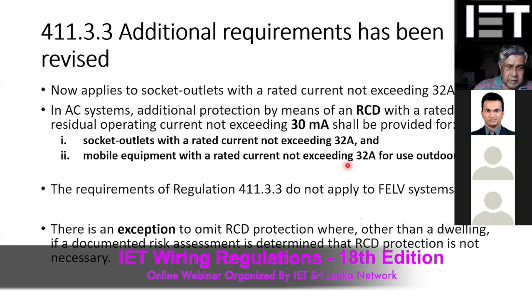And when you look at this, this rule is not applicable if you are going with FELV, that is, functional extra low voltage. Sometimes there are certain locations where we want to extend our earthing system to the extra low voltage system as well. In that case, if you are following functional extra low voltage, then you don't have to stick to this rule. That is the only exception. Other than that, if you have any circuit with a socket outlet or mobile equipment of less than 32 ampere, then that should be protected with a 30 milliampere RCD.